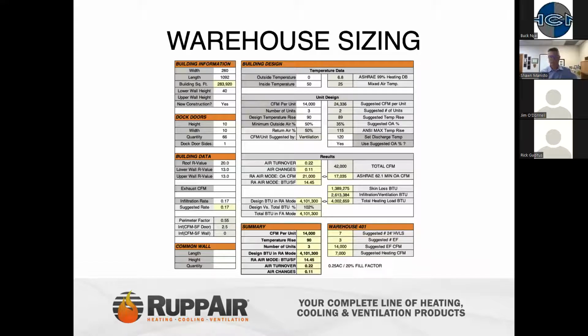So kind of a wrap up. As far as warehouse heat sizing, this just shows one of our tools we utilize for how we size a warehouse. All the criteria we talked about early, from the size of the building, the dock doors that are in the building, R values that exist. It gives us some suggested infiltration values, and then you can actually adjust that to run what you need. Basically, other losses that exist based on ASHRAE codes. What you want to have for an outside temperature and indoor temperature.